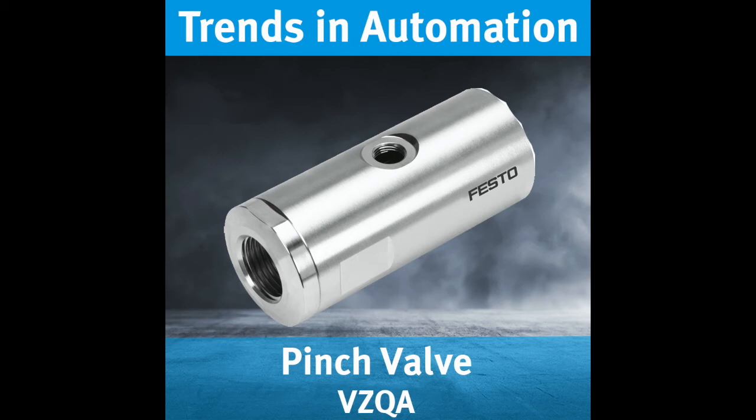The second feature of the VZQA is the lifetime of the valve. Now, in many general purpose process applications, valves might only be operated a few times a day or a week, so life cycles aren't so important. But in filling and dosing, valves might be opening and closing every few seconds. So it's necessary to have a valve with great longevity so the customer is not doing maintenance on them once a week. For comparison, a ball valve, which is one of the most prevalent types of process valves out there, usually averages about 50,000 life cycles, whereas our pinch valve is tested to a minimum of 500,000 life cycles. That's 10 times the amount.